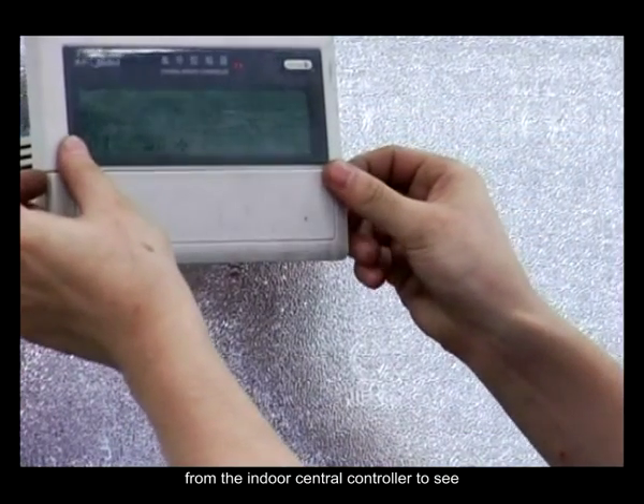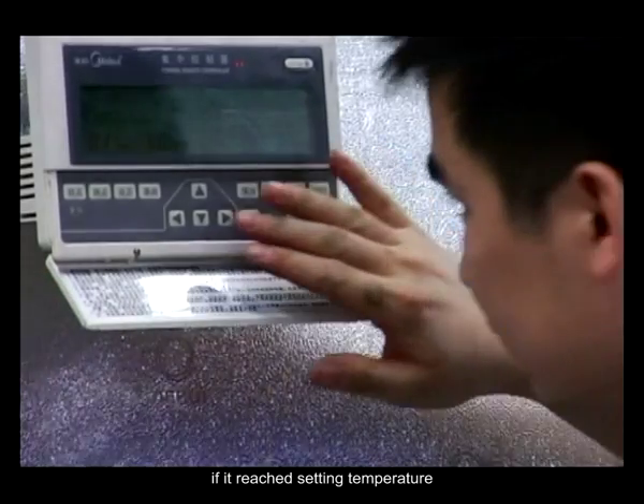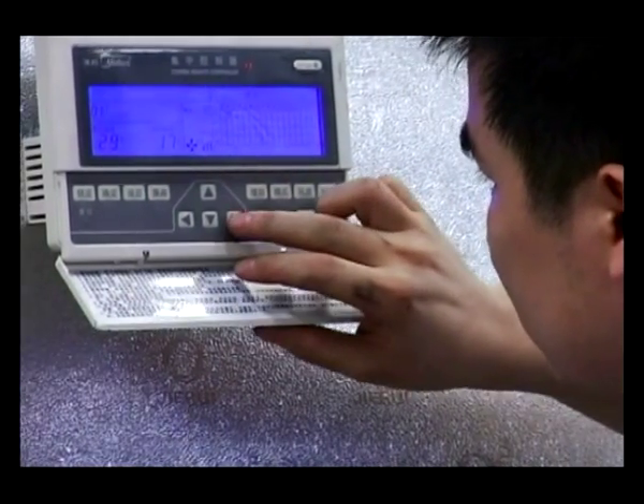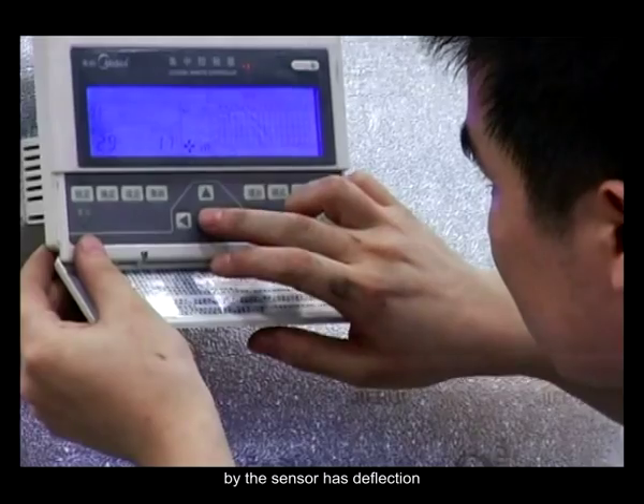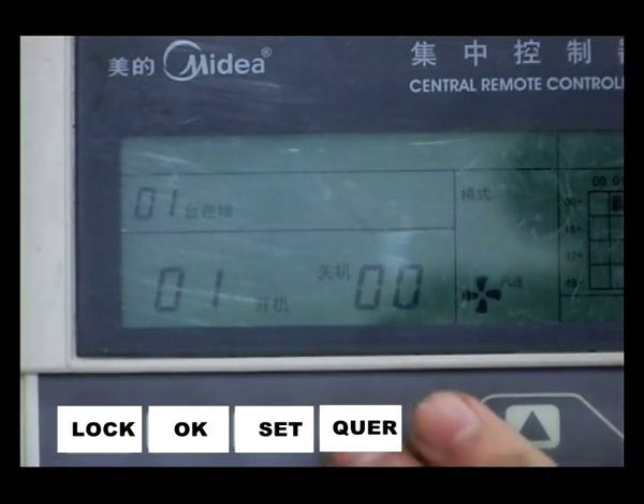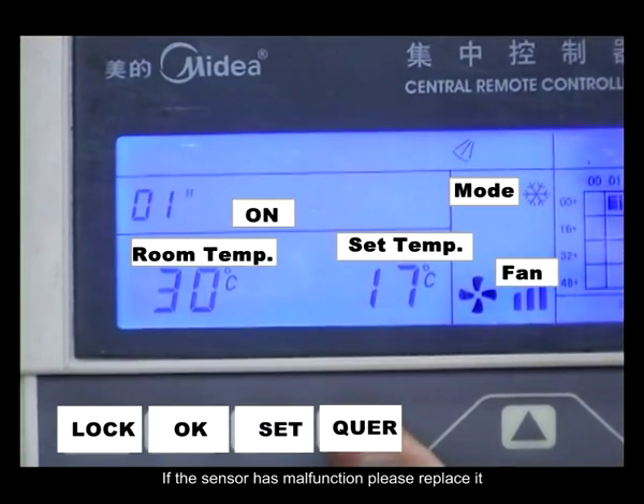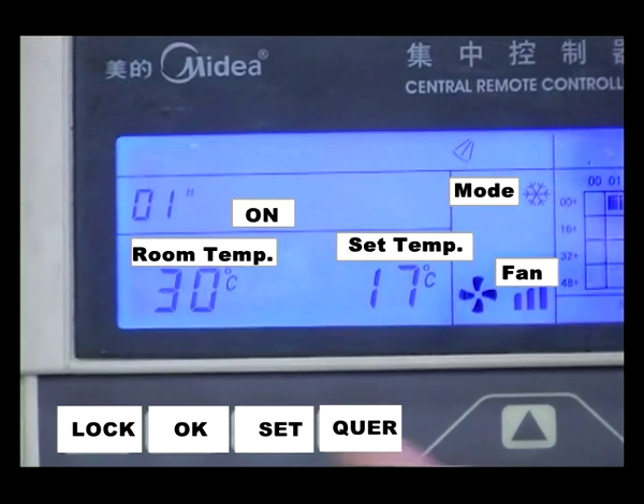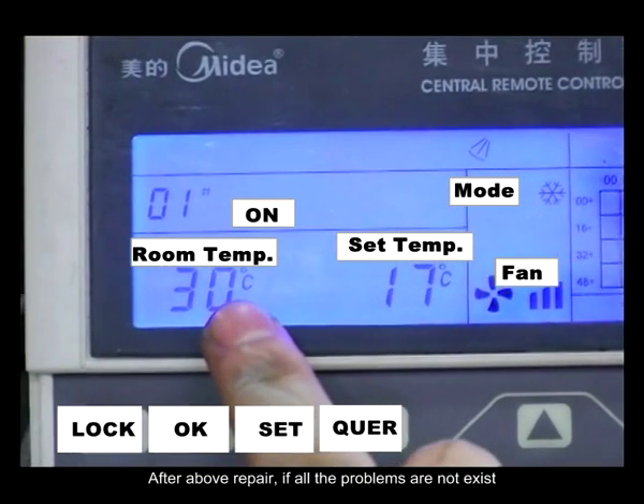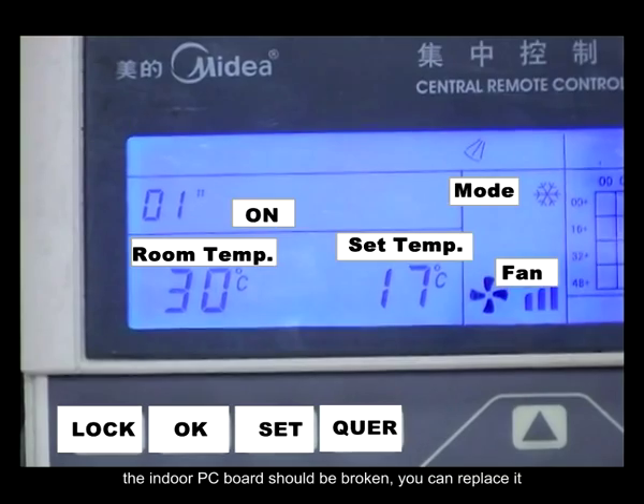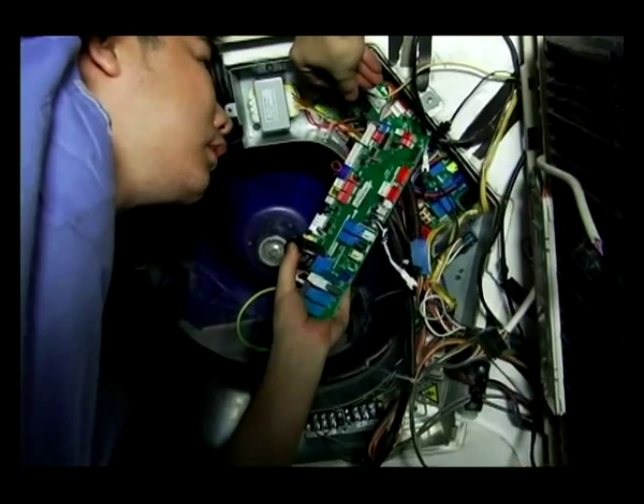You can also query temperature sensor T1 from the indoor central controller to see if it has reached the setting temperature. Check if the temperature data collected by the sensor has deflection. If the sensor has malfunctioned, please replace it. After the above repairs, if none of the problems exist, the indoor PC board should be broken. You can replace it.